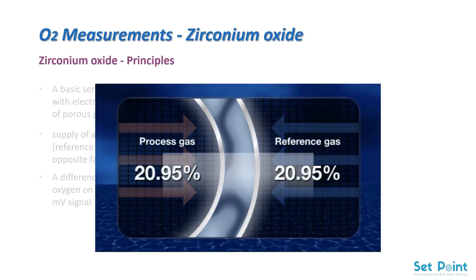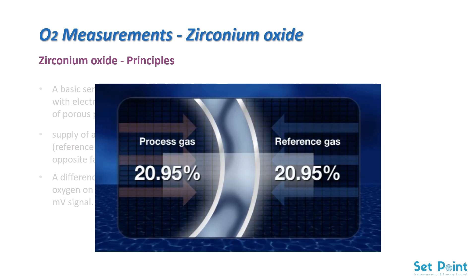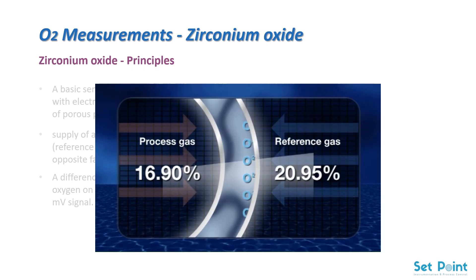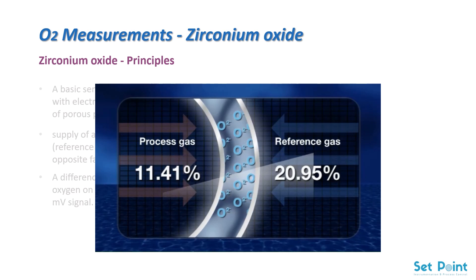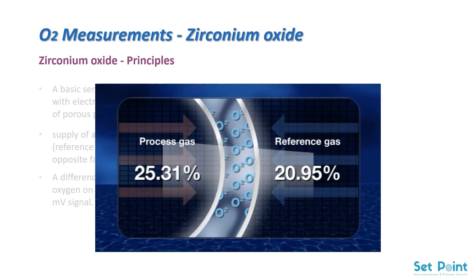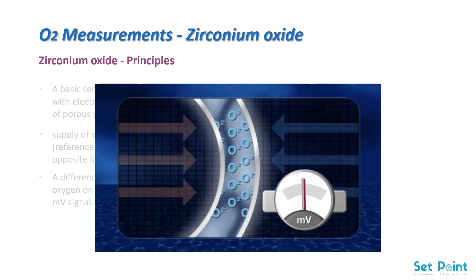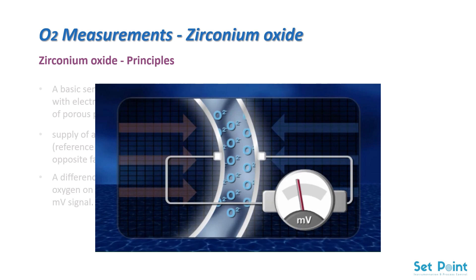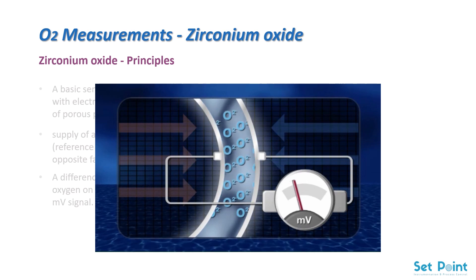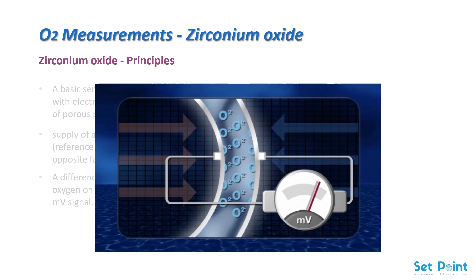When the oxygen concentration is equal on both sides, migration of the oxygen ions through the zirconia is zero. Where the concentration differs, the migration will increase to try to re-establish equilibrium. The differing reaction at the two electrodes generates a corresponding potential difference that can be used to measure the oxygen concentration in the process gas.